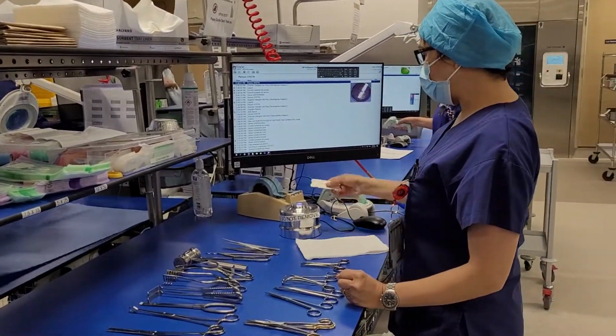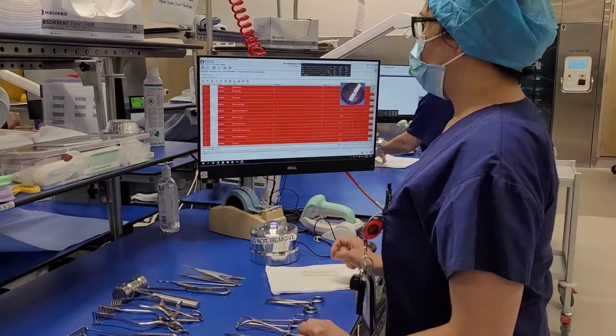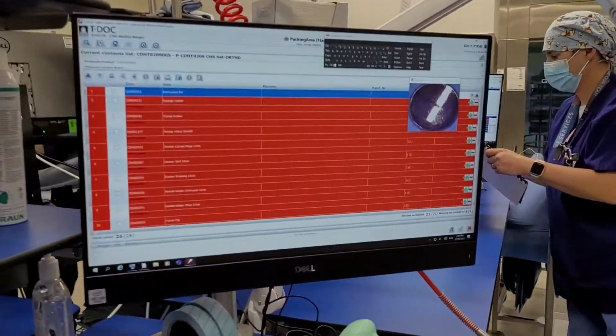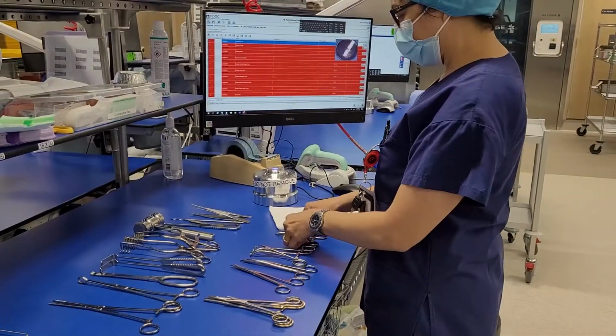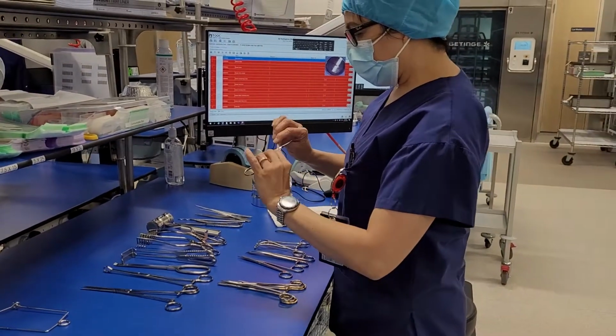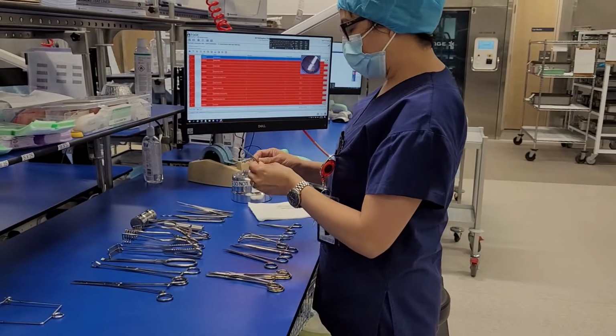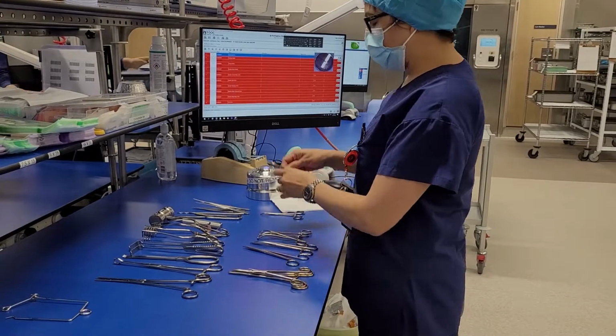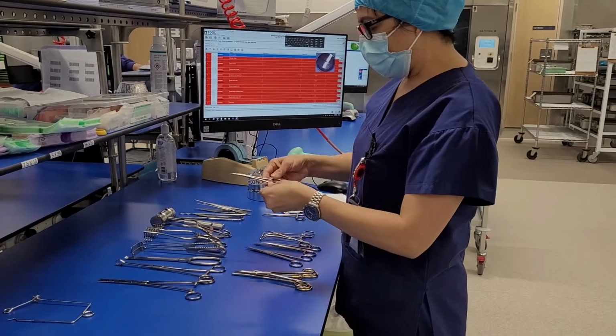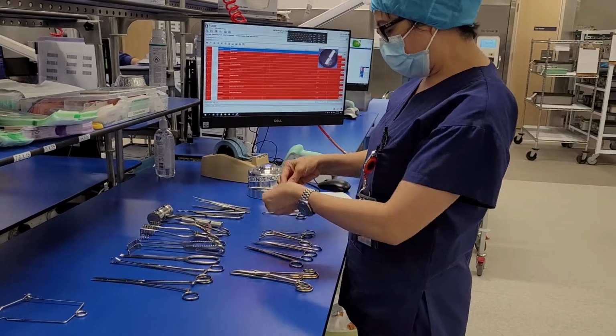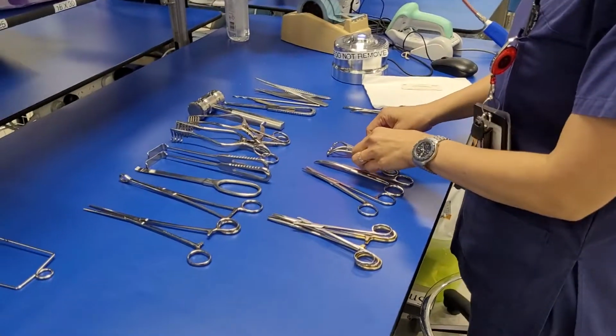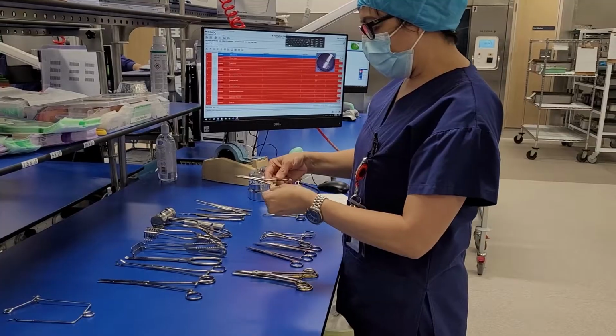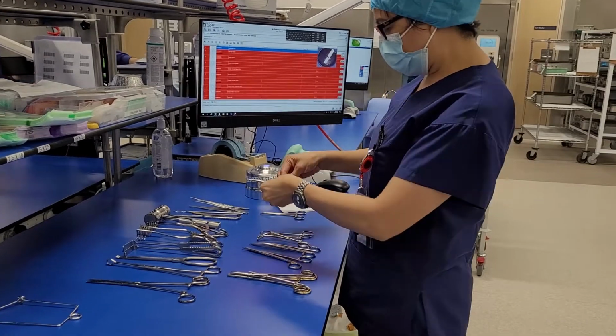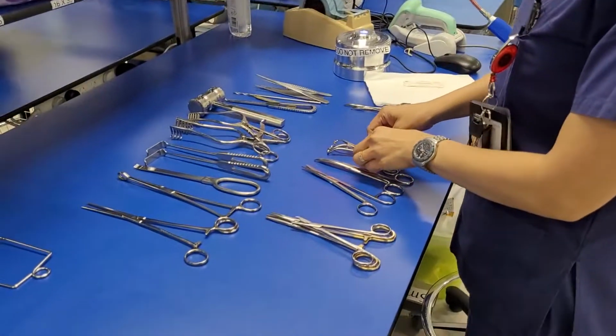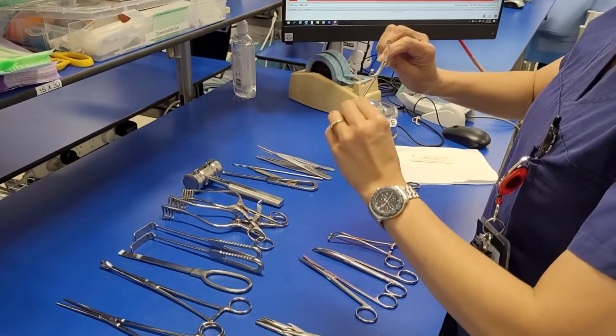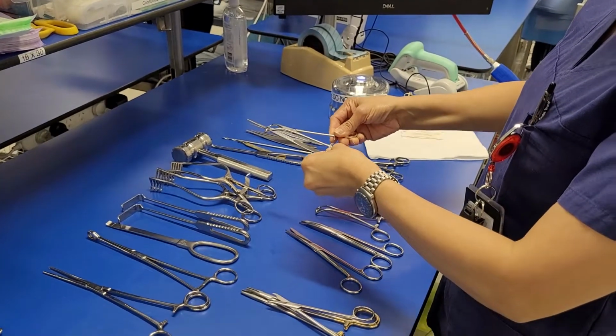Through scanning the barcode in the T-DOC system to view the list of the items, all instruments must be checked for cleanliness and working condition in accordance with the manufacturer's instructions for use. Special care must be taken to ensure that all lumens are free from debris. All surfaces, joints, hinges, and crevices must be clean. Any debris left on these areas could cause damage over time and will create a reservoir for microorganisms.